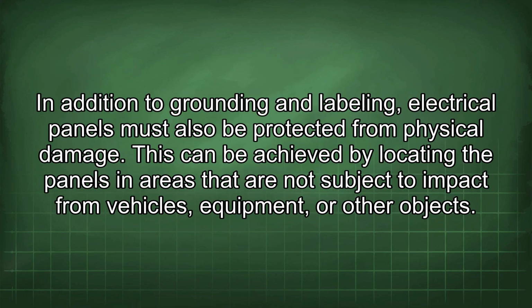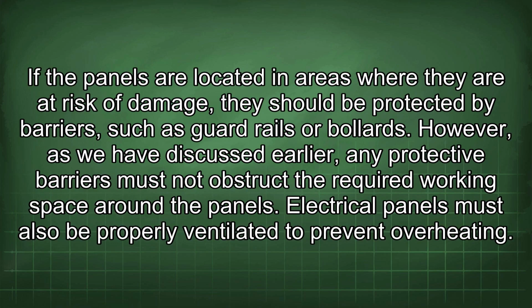In addition to grounding and labeling, electrical panels must also be protected from physical damage. This can be achieved by locating the panels in areas that are not subject to impact from vehicles, equipment, or other objects. If the panels are located in areas where they are at risk of damage, they should be protected by barriers such as guardrails or bollards. However, as we have discussed earlier, any protective barriers must not obstruct the required working space around the panels.